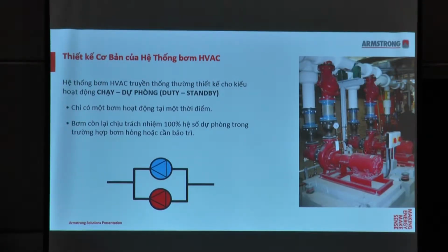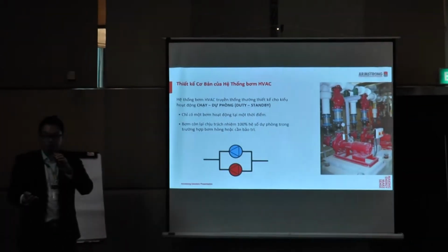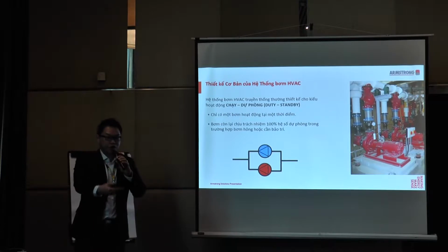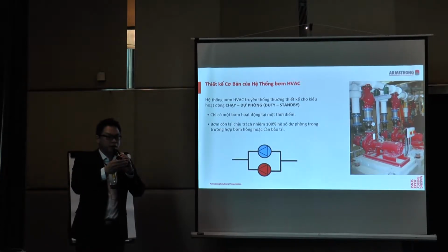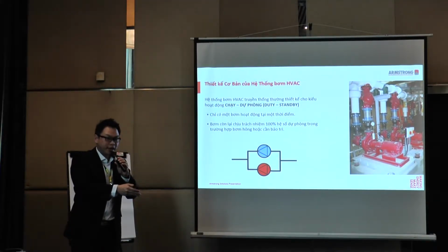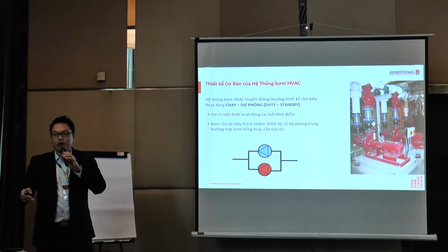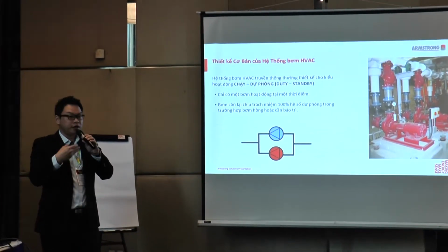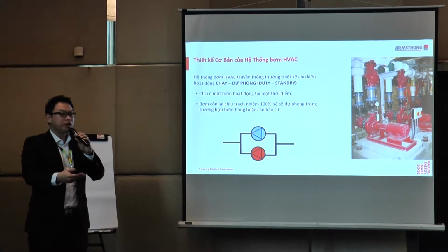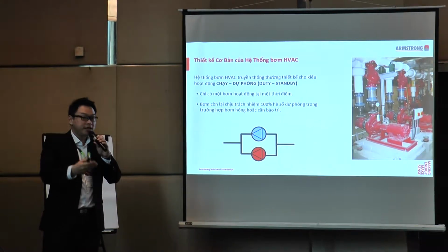I believe in some of your existing designs, as engineers, consulting engineers or designers, you have your pumping system designed as duty standby. Am I right? As you can see here, this picture looks very familiar to you. You use a traditional end suction pump with one pump operating at one time and the other on standby, giving you 100% redundancy in case of a failure or a maintenance requirement.